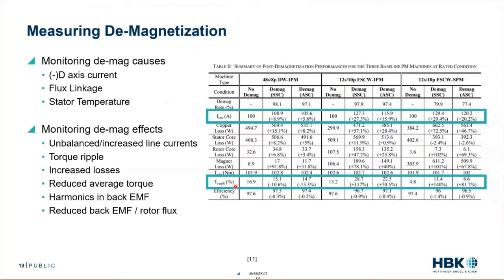We could also see torque ripple. We have an increase or decrease of 10% torque ripple in this given configuration, and an increase of 100% or 70% torque ripple in these other two. These are things we can pick up on really easily from a measurement perspective.